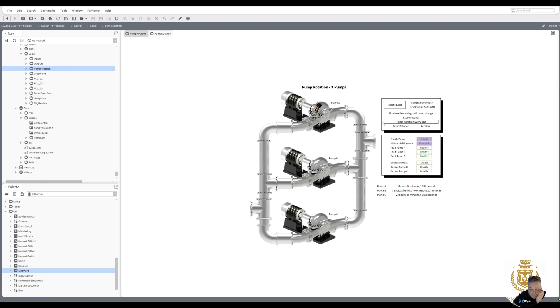We're 57 seconds before we're going to rotate. The next pump that's going to be rotated is actually B, so you will see that this will start and this will stop. We'd probably be better putting in our logic some off delays so we'll basically have two pumps running for a period of say 30 seconds.